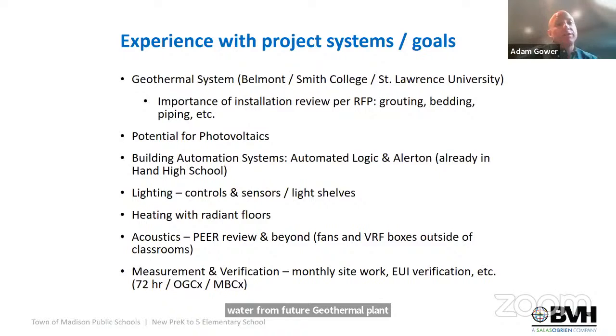We definitely see the importance of the installation review described in the RFP for the geothermal, as far as reviewing the grouting, bedding, and piping. The grouting is very important for thermal conductivity, for your performance in delta T's, as well as getting air out of the system so you have the right pitches on your piping. We don't want to trap air in the well field.